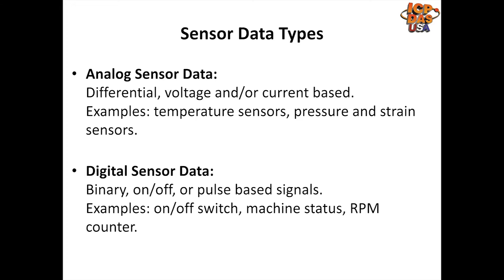When selecting a data acquisition module, this is the first thing you're going to look for. You need to think about the types of sensors you have and what kind of data you are trying to collect. DAQ modules come in a very wide array of I/O configurations, and you can get either digital or analog DAQ modules — or modules that do both. You can also get modules specifically designed for specific sensors such as thermistors, strain gauge counters, or pulse width modulation. Those specially designed modules will usually be more accurate for use with those specific sensors than a general-purpose analog or digital module.